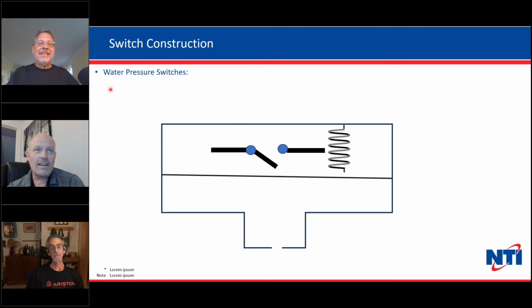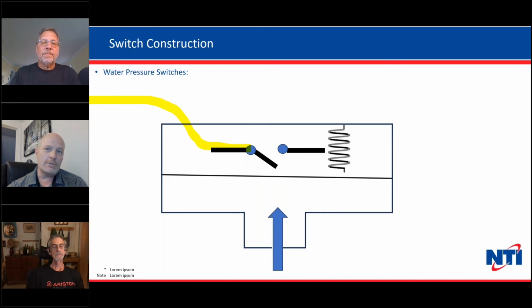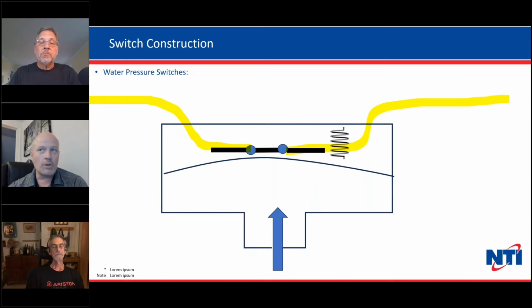This is a cutaway representative of the Nason water pressure switch that's on all of our LX and TI boilers. The way this works basically is there's a rubber diaphragm in the middle here. When water enters through the hole in the bottom, it will push on the diaphragm, and when it does that, it literally just activates a set of contacts. The little spring is in there. So there's our electricity coming through. It can't pass through until we add some water pressure. Once we add sufficient water pressure, you close the switch and compress the spring.